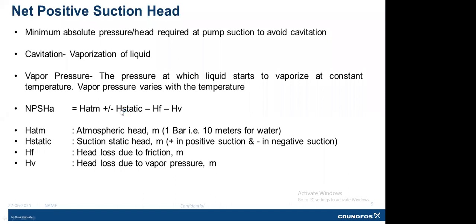HF is nothing but the head loss due to friction in the pipeline, and HV is nothing but head loss due to vapor pressure. So how do we calculate the static head? By measuring the difference between the water level and the pump center line. That would be the static head. Head loss due to frictional losses we calculate using formulas, by taking into account the pipe size as well as pipe roughness and pipeline length.